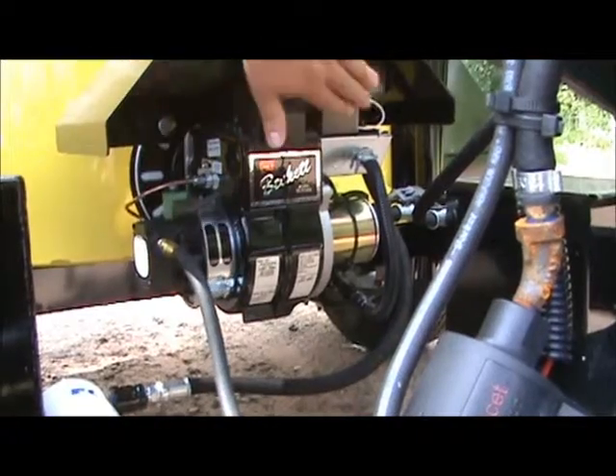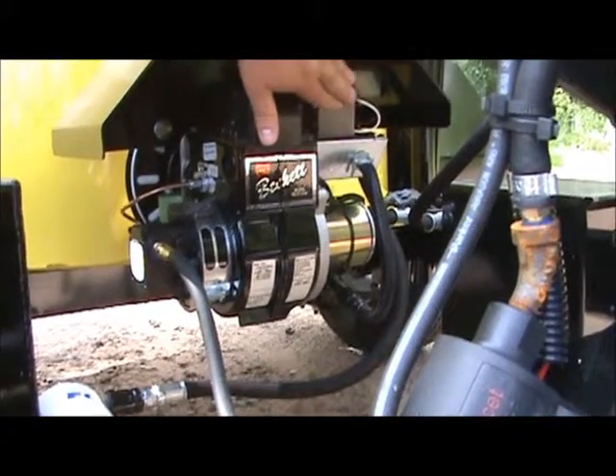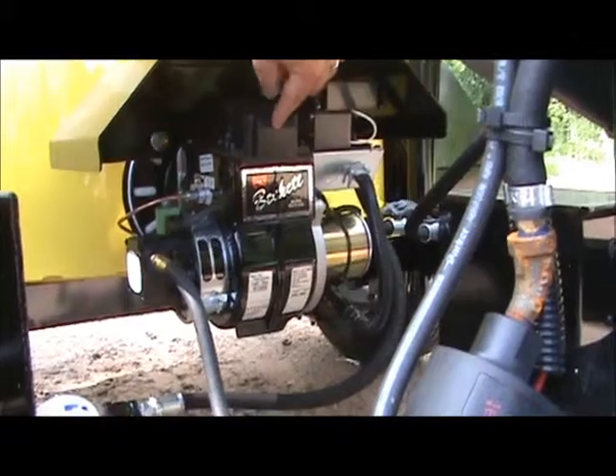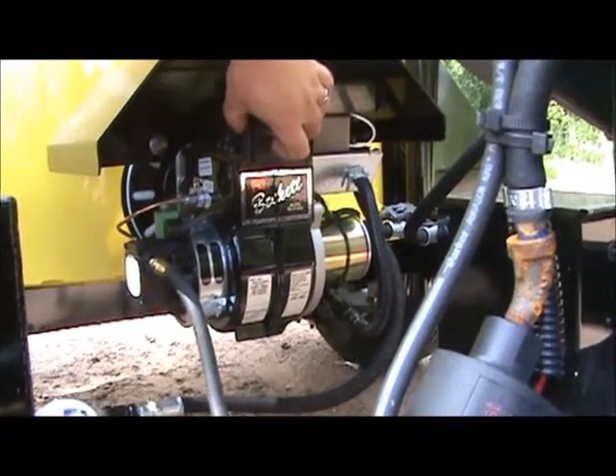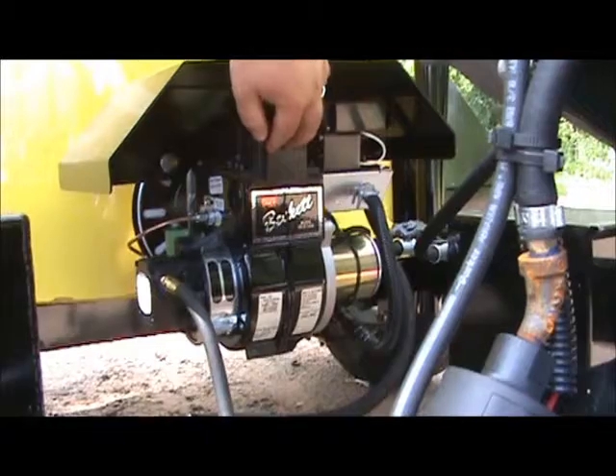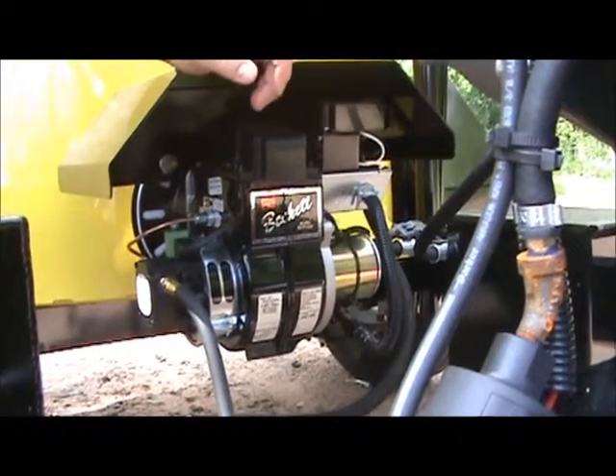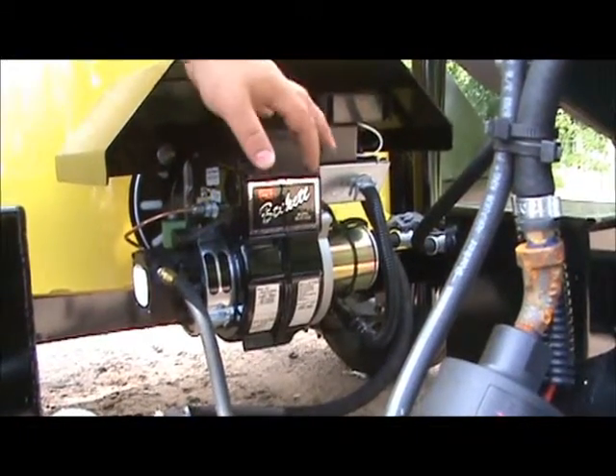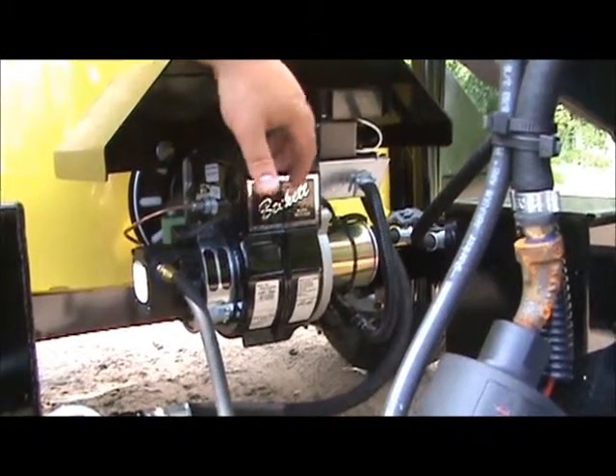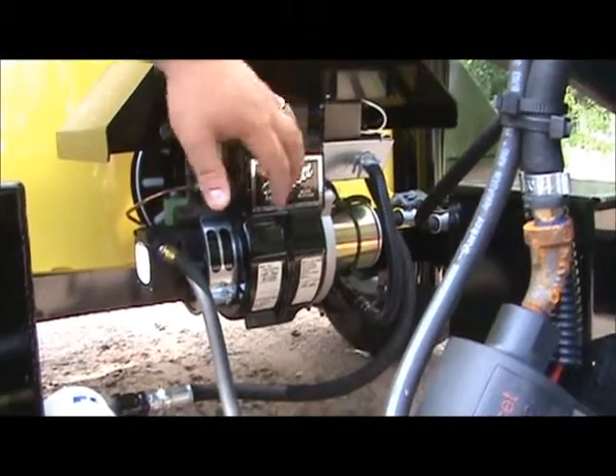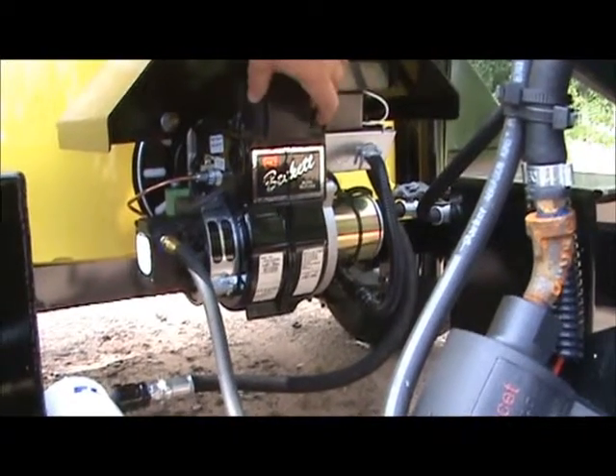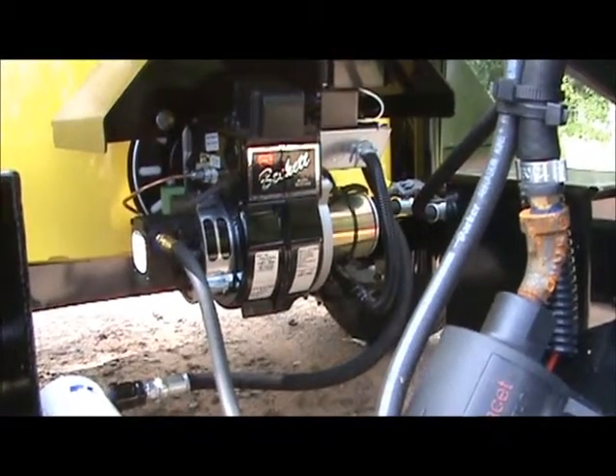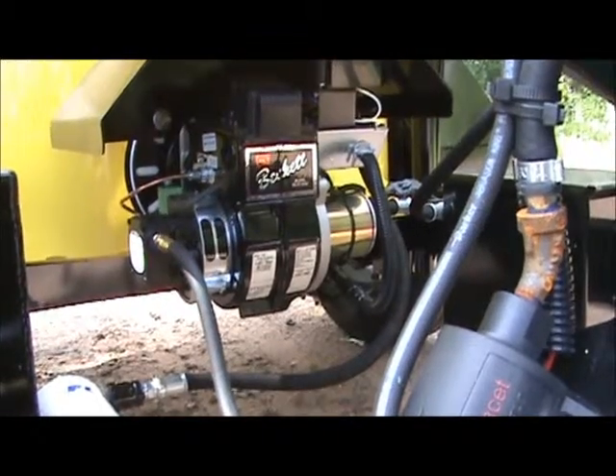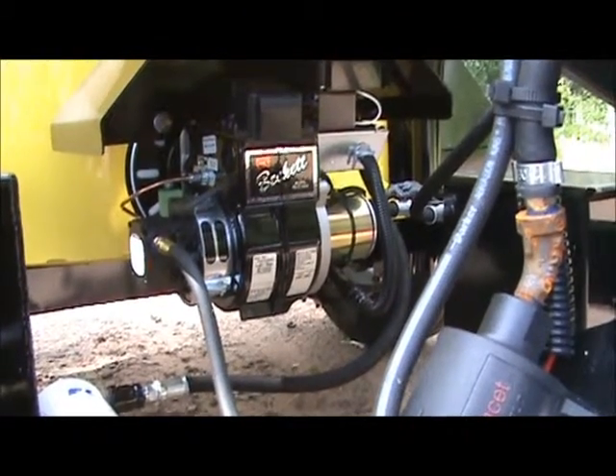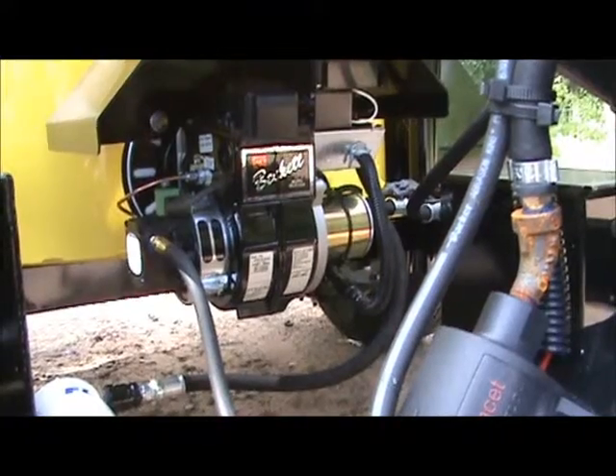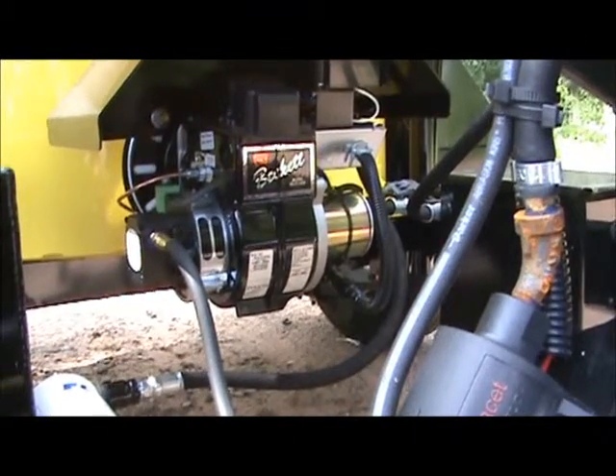When our thermostat calls for heat, this primary control, which is the main brain box of the burner, tells the black box here to send spark down there. This is actually our ignition transformer. This sends the spark to light the burner. Once the burner establishes a flame, there's a flame detection device inside of that. It's called the photo eye. It's located on the top of this black transformer. Once it sees that it has established a good flame, it's going to light and stay lit. If it doesn't light, it's going to try for reignition, and if it doesn't light the second time, it's going to go into a lockout mode.